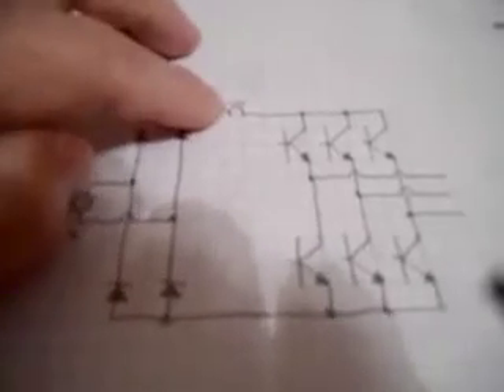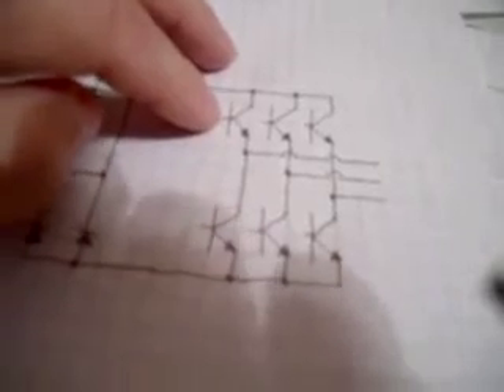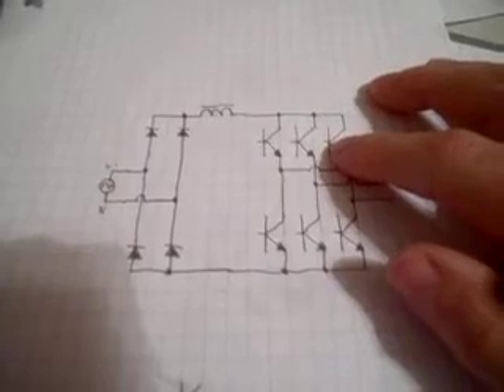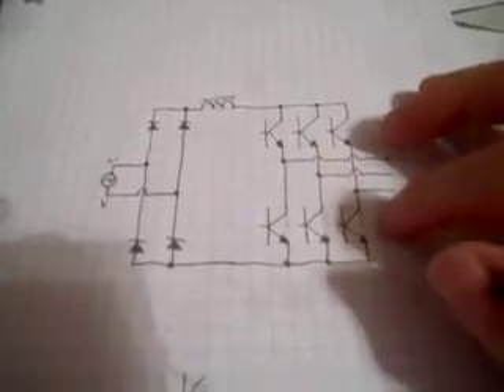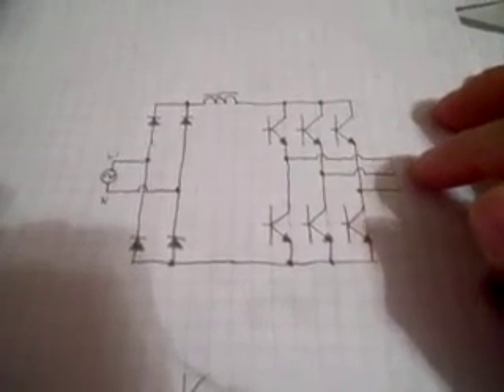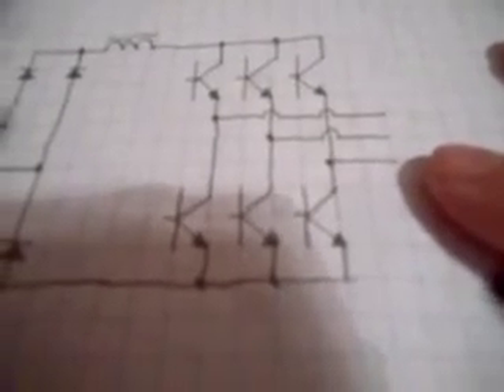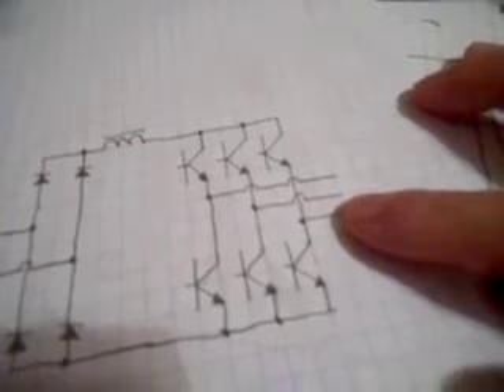This is basically your full-wave bridge right here. It's just connected up a little bit differently, and right here's your filter. And right here is your insulated gate bipolar transistors, and your firing packages would be connected up to these gates that are on each of these transistors. And it would basically do what I just described in the other circuit. And the firing package that would be connected up to these would basically just vary the frequency to control the speed of the motor. Higher frequency goes faster, lower frequency goes slower, and your motor has to be rated for something like this.